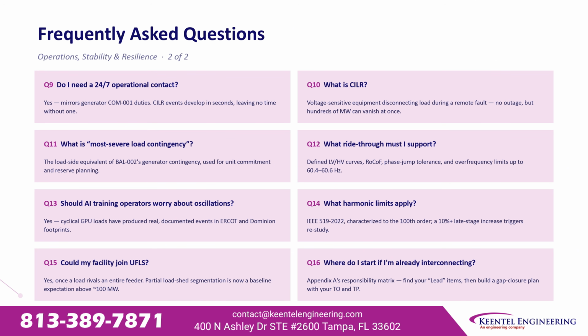What ride-through must I support? Low and high voltage curves, rate of change of frequency, phase jump tolerance, and over-frequency limits to 60.6 Hz. Should AI training operators worry about oscillations? Yes, cyclical GPU loads have produced real documented events already. What harmonic limits apply? IEEE 519, characterized to the 100th order, with restudy triggered by late-stage increases. Could my facility join load shedding? Yes. Once it rivals a feeder, partial segmentation is now a baseline expectation. Where do I start if I'm already interconnecting? Appendix A's responsibility matrix, find your lead items, then build a gap closure plan.